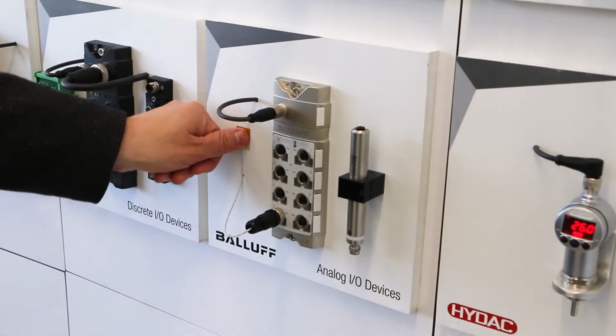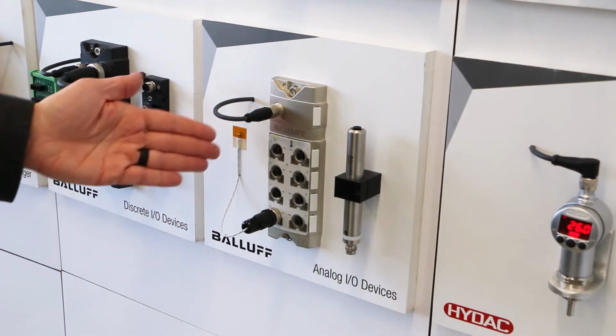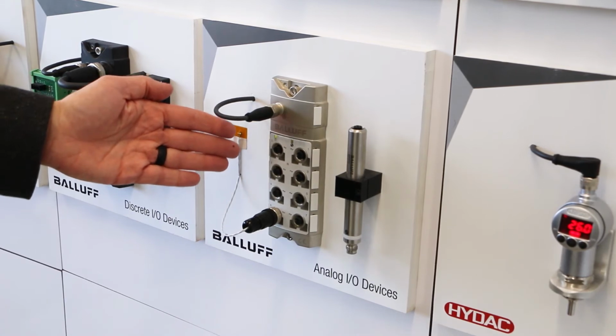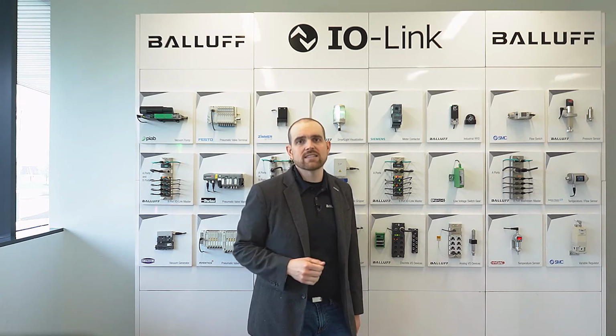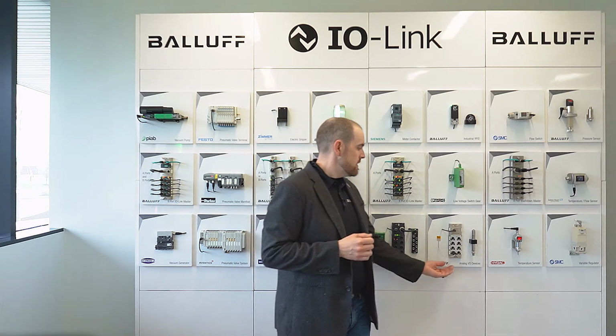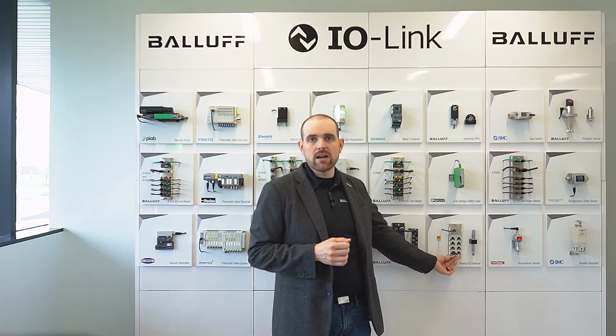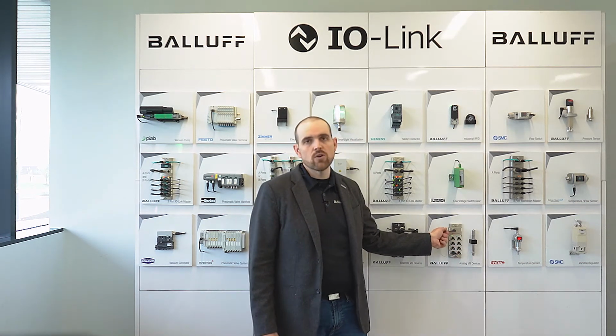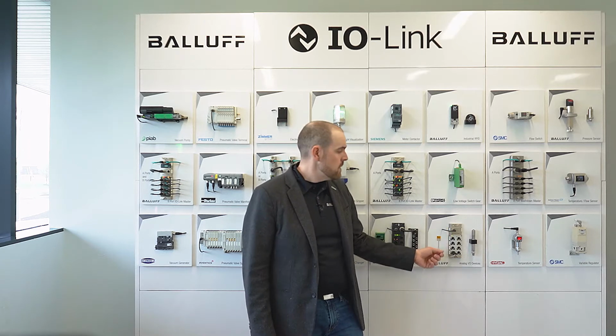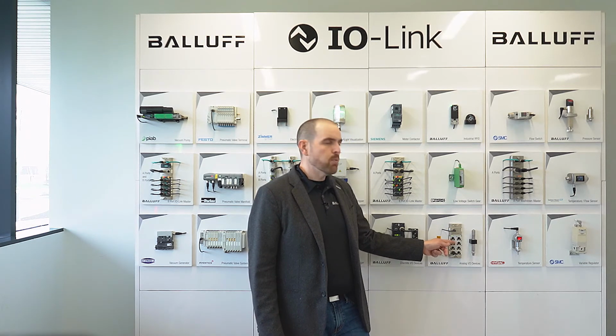I really love this device. This is an analog input. Typically you have to have an analog slice in your PLC, have grounding in the cabinet, and make sure your shielded cable is protected. This actually collects the analog signals right out on the machine, does the analog to digital conversion there, and then sends it over an IOLink connection. What's cool is you could tell each port to be something different—one can be 4 to 20 milliamps, one can be a temperature value.